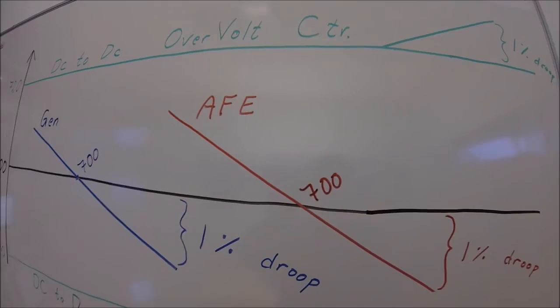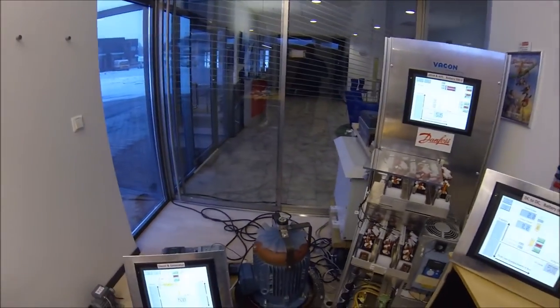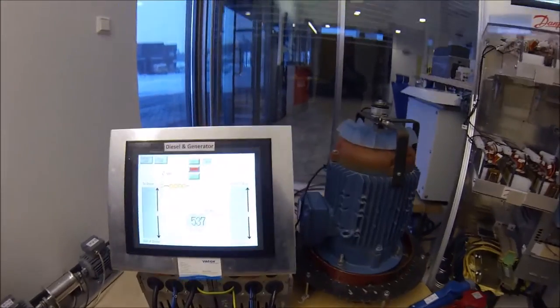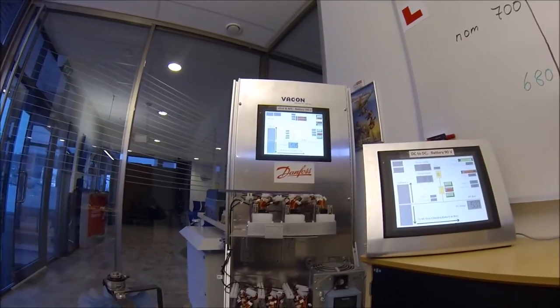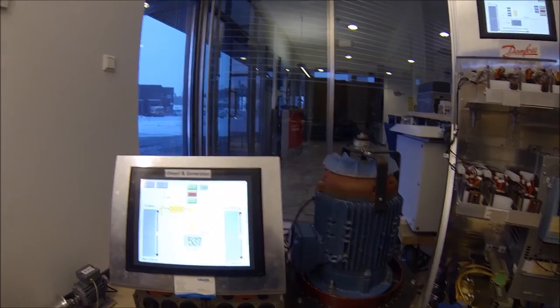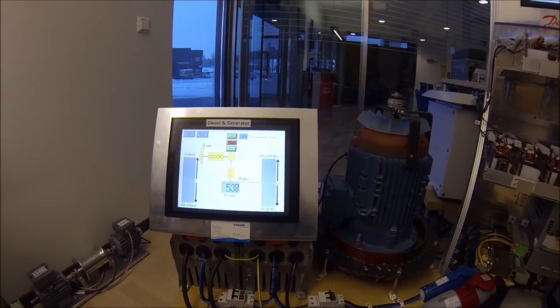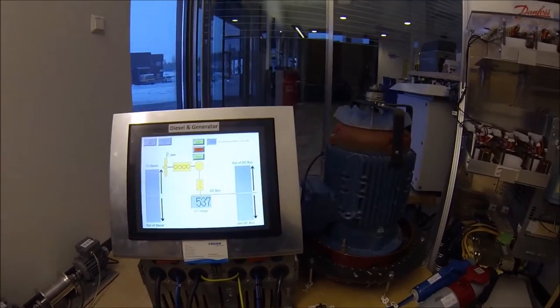In the real world, the generator application is not alone. It usually sits together with a grid application, active front ends, and a DC-to-DC converter. Here in our simulator we have all these applications on the same DC bus. When running a DC bus with all these energy sources, we have to calibrate them. We have selected 700 volts as a nominal DC voltage — the reason being that one of our full-scale projects had 700 volts and our customer came for training on those same numbers.